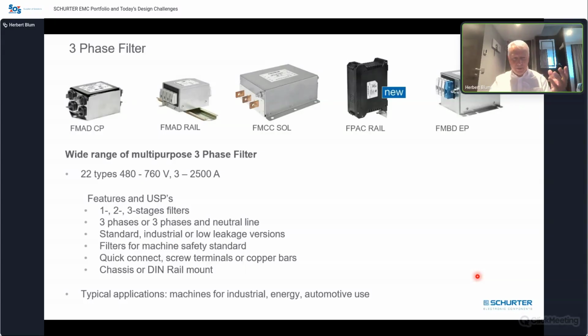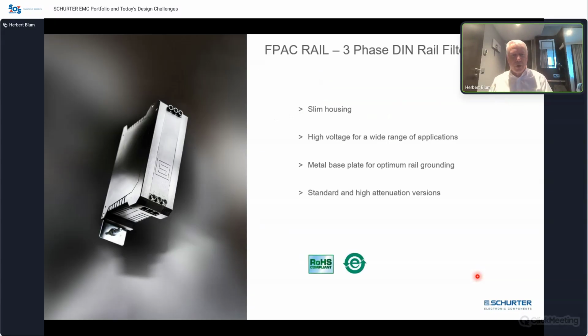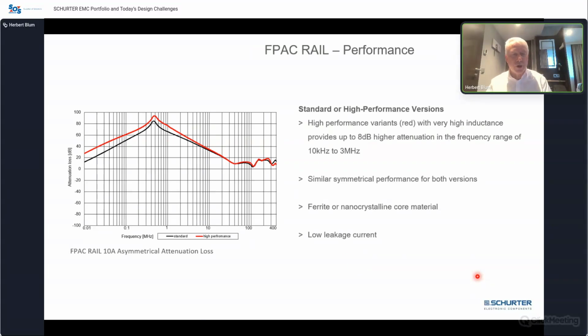Now, what is special here, or what kind of application trend do we see? First of all, we made the same slim housing for the control cabinet. So it's a bit the same, plastic housing, compact filter. Here we have two versions. The difference is not that big, but we try to do a standard and a high performance version. It's still quite good when you look at the frequency range here, starting at 10 kilohertz. I have to say the 0 on this graph is in the middle, but it goes up over 80 dB of attenuation. So you reach about 80 dB at the highest point here. And this comes because we have ferrite or nanocrystalline core material. So quite good performance for the compact size.